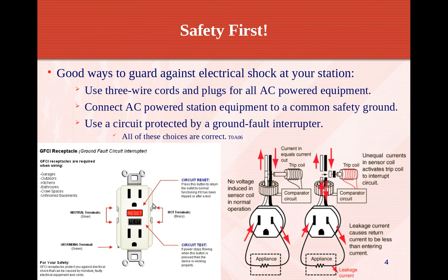So here's your GFCI receptacle. You've all seen that. You got a test button, a reset button. And the way this works is that it compares the power of the hot lead versus the cold lead. So power in has to equal power out. If there's an imbalance, there's something wrong and it trips it. And that's basically how the GFCI works. GFCIs you want to use at any wet location, outdoor location, crawl space, unfinished basements, that sort of thing. They're not that expensive either.